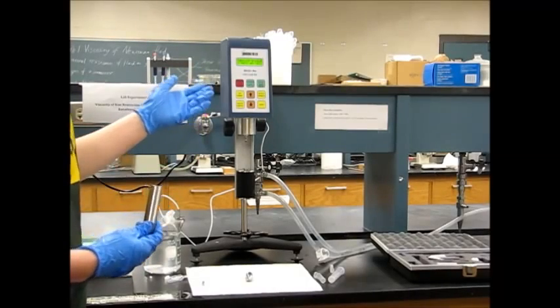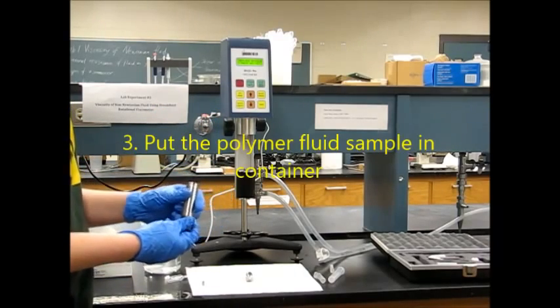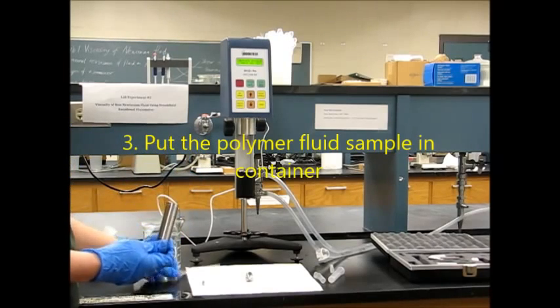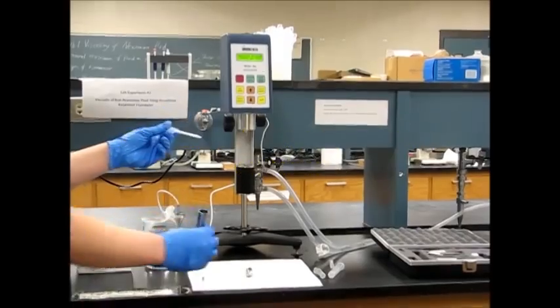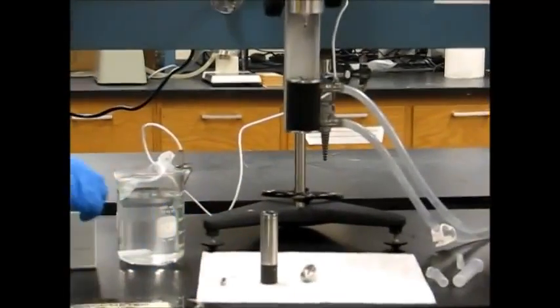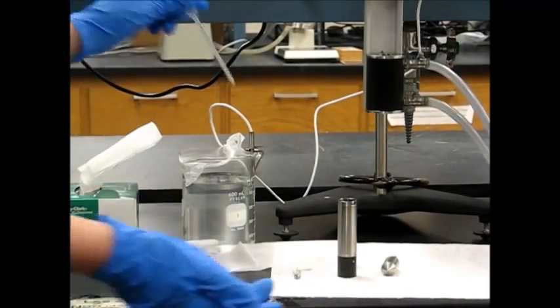Now it's telling us to replace the spindle. But before we can do that, we need to fill our sample container around 25% full with our polymer solution. It's going to take about three squeezes to get to 25%. Be careful because this fluid is very viscous and it will make a mess.